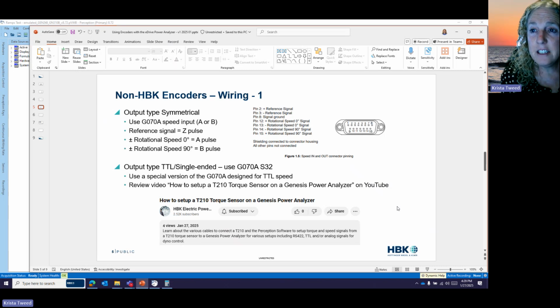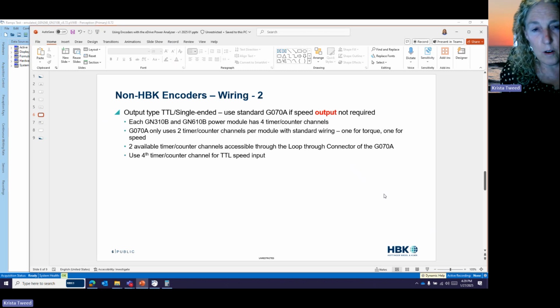Now, if you also have T40B and T12s, and you need to have a standard G70, there is the possibility of using that standard G70 to measure a TTL speed encoder, as long as you don't need speed output. You don't need that signal to be split by the G70 and send that speed signal directly to your automation system. So that's the way that we do that: each GN310B and 610B power module actually has 4 timer counter channels. And the G70A only uses 2 of those timer counter channels per module with its standard wiring. It's designed to be used with both slots A and slot B. And so that leaves 2 available timer counter channels, and we can take advantage of that.